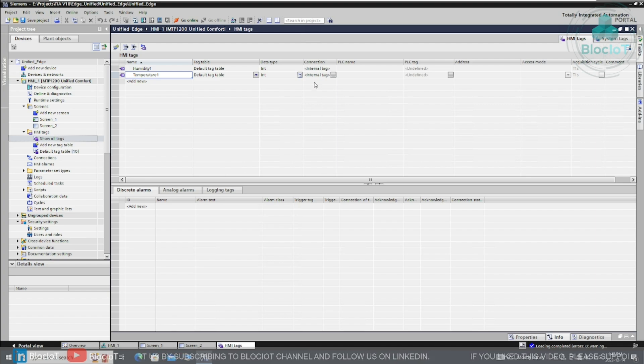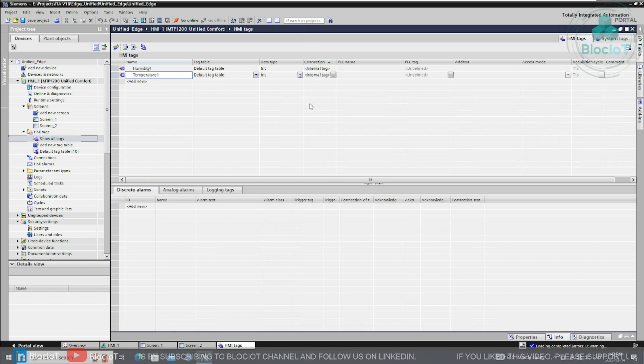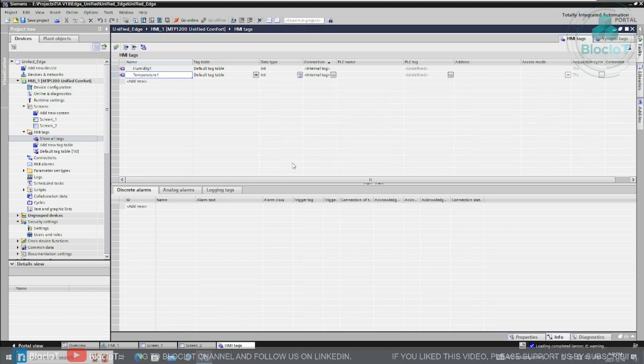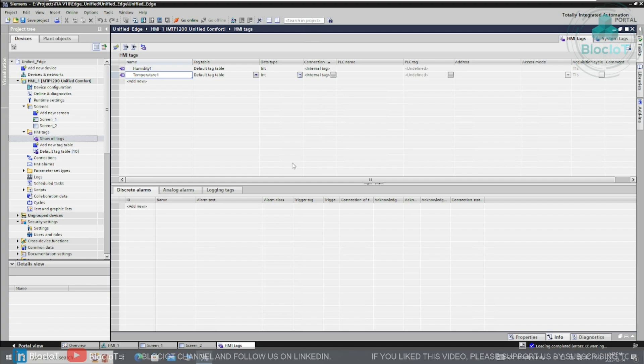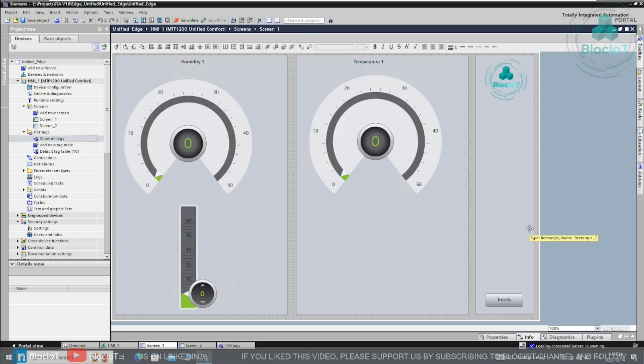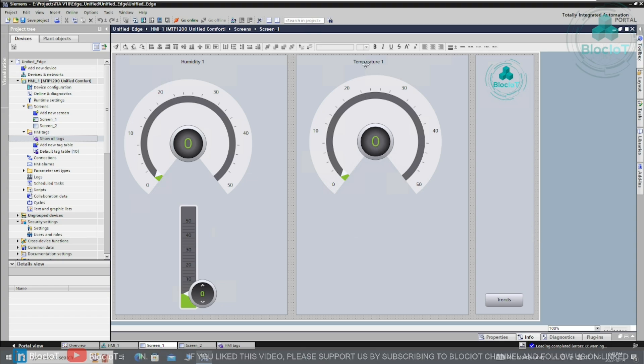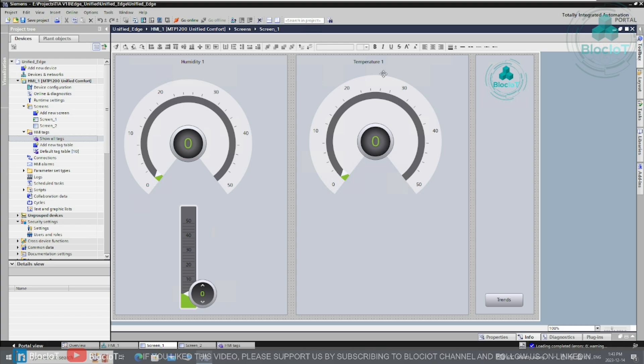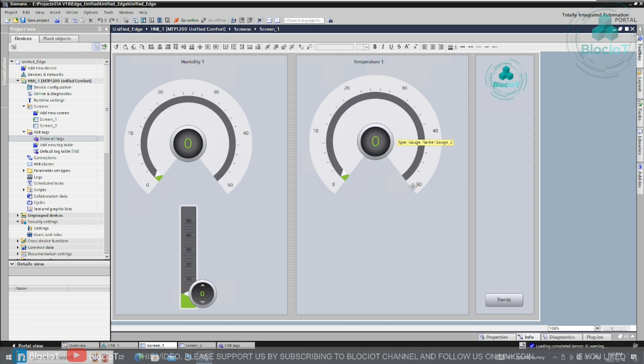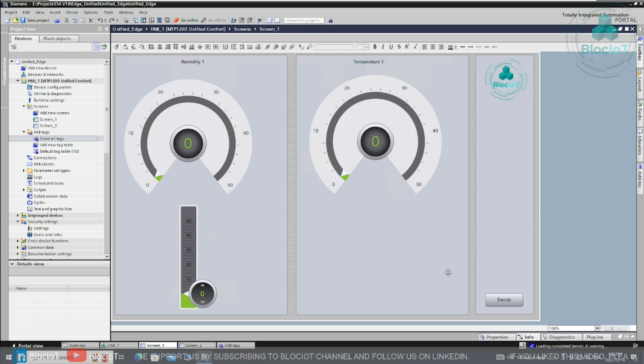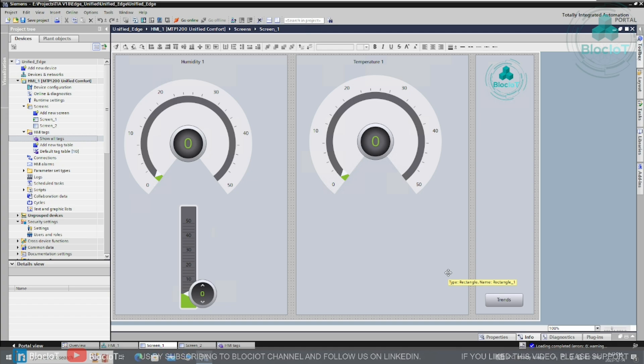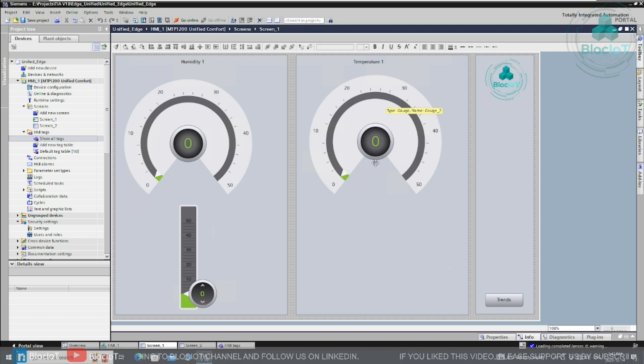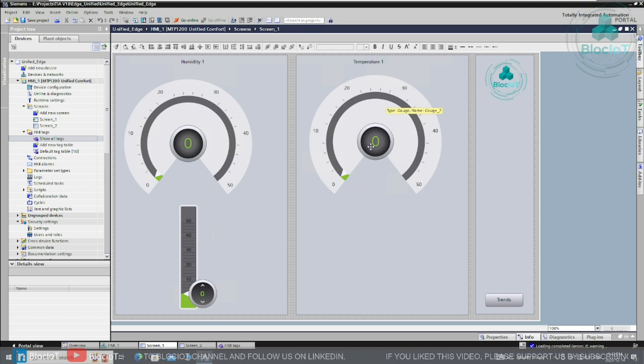These objects are connected to two tags and we name them after our MQTT topics which are humidity one and temperature one. As you can see these are internal tags so the communication between the HMI and our PLC will be MQTT, not PROFINET, not MODBUS or something similar. So here's how the project will work. We have a gauge that shows the current value of temperature one, and if you remember from the previous video, temperature one is getting updated by our S7-1200 CPU over MQTT and LMQTT client library.